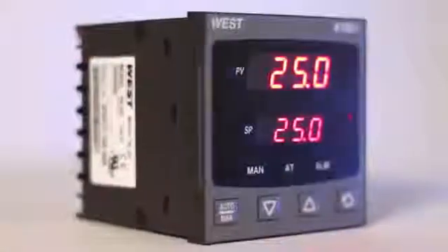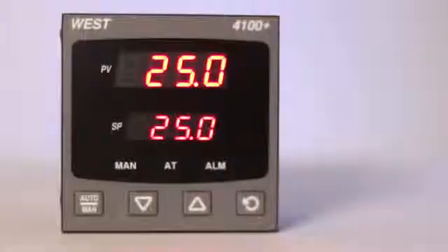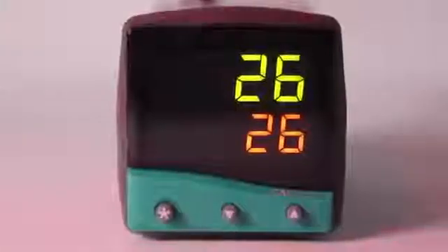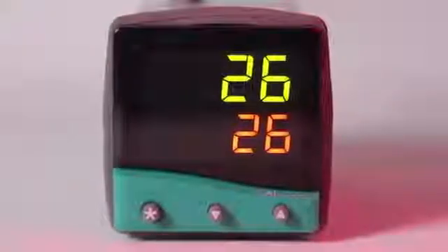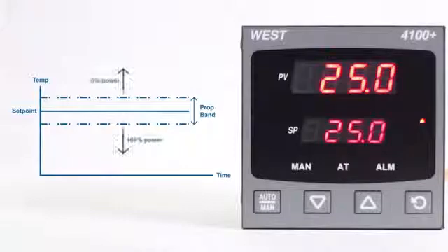A proportional controller doesn't just turn its output states to on or off, it can adjust them anywhere between 0 and 100% of available power. The direction of output is still important with proportional control. With reverse acting, the output is slowly moved from 100% through to 0% as the process rises. If the process is properly tuned, the output power from the controller will precisely match the requirements of the process and therefore achieve completely stable control.